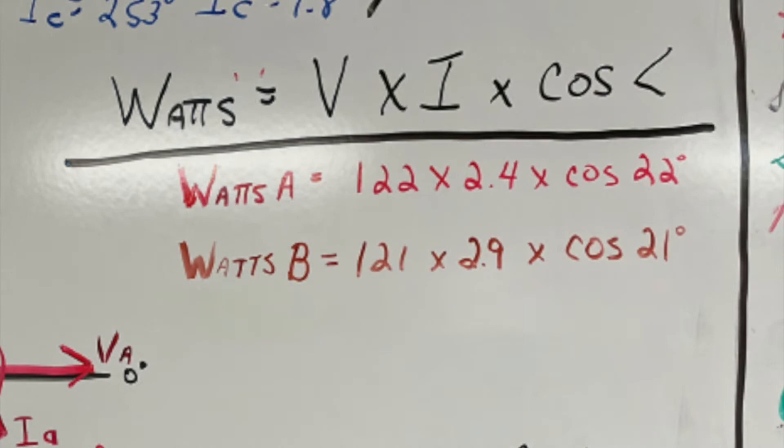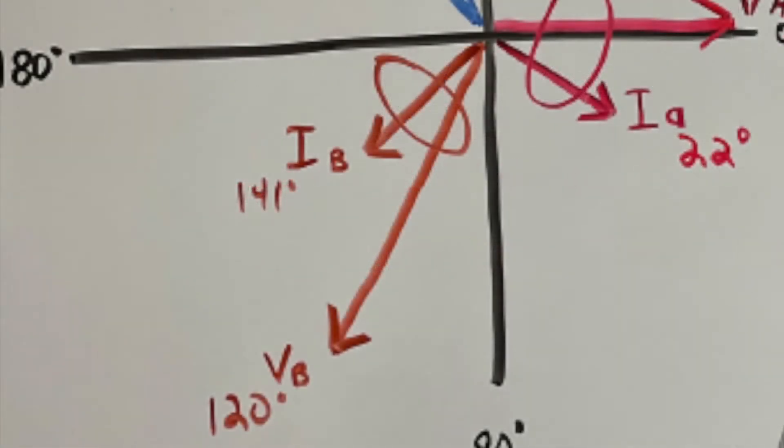And we're going to go to phase B where we have 121 volts times 2.9 amps with the cosine of 21 degrees. If we look at the chart, we're lagging by 21 degrees from voltage B.